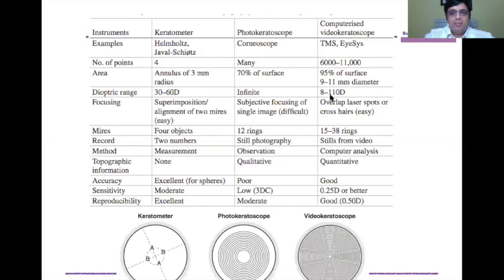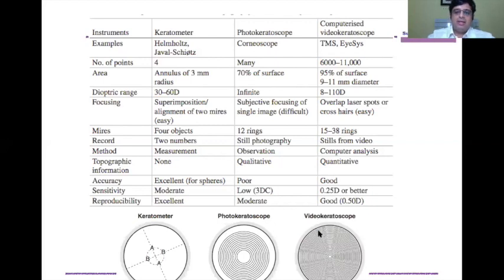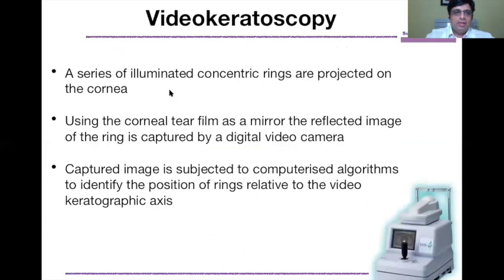The video keratoscope has improved diopter range coverage up to 110 diopters, with up to 38 rings, accuracy of ±0.25 diopters, and good reproducibility. Video keratoscopy uses a series of illuminated concentric rings projected on the cornea. It uses the corneal tear film as a mirror, and the reflected ring image is captured by a digital video camera. The captured image is subjected to computerized algorithms to identify the position of rings relative to the video keratographic axis, giving angulation, then radius of curvature, and finally the diopter K value.